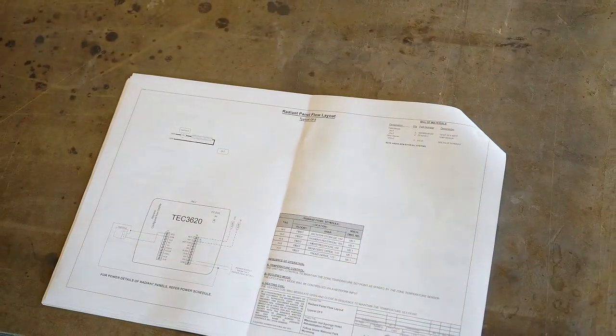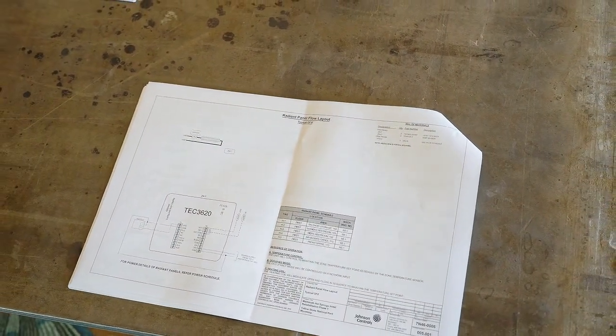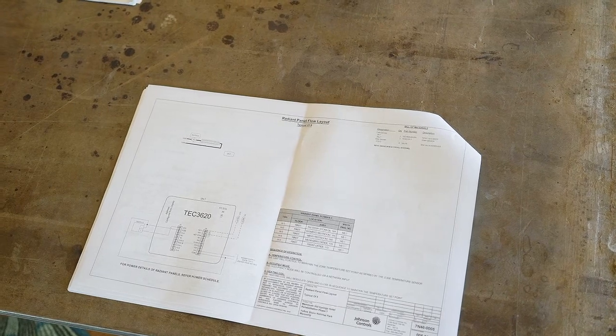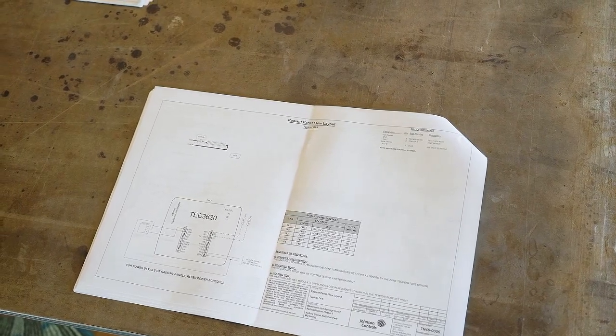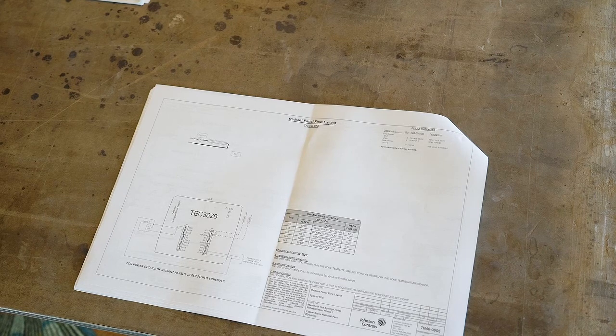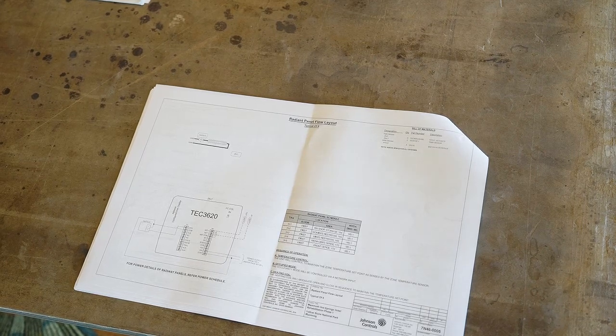And then that'll bring us to the next section, which is the radiant panel, which is baseboard heat. So there's like 8 units throughout the building. They're labeled H1 through H8. Those are controlled individually by a TEC controller. And those are the ones that have the LCD bigger screens on them. Okay, so there's 8 of those throughout the building. And those are also part of our BACnet, so those points are pulled into the front end.